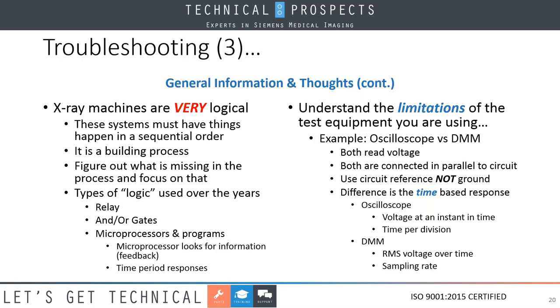I bring this up to your attention because you'll find that there are switching power supplies in X-ray machines where typically you may only get a tenth, maybe 3/10 of a second, in which case then the digital multimeter will give you an erroneous reading. You'll need to pull out your oscilloscope to read that particular voltage.